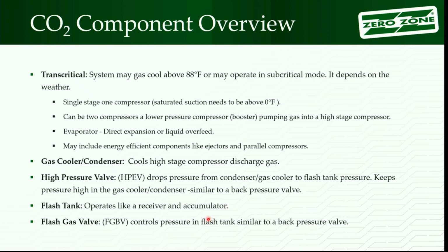And then when you do transcritical systems, it may include some energy efficient components. Ejectors, we'll talk about that in a minute. We'll talk about parallel compressors to gain some energy efficiency with it. So after the compressors, we have the gas cooler condenser. And if you look at them, they look the same for the most part. If you were looking at them at a distance, you wouldn't know if that's a gas cooler or a condenser, or if it's from an HFC system or a CO2 system. So it's doing what we're used to with HFC systems. It's taking the heat of compression and putting it out in the air, getting rid of that heat. So that's really what it's doing.